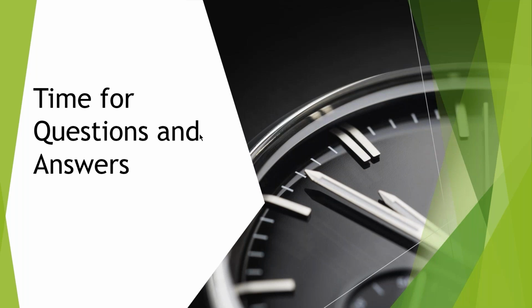For instance, what I was showing here, if you buy really good equipment, have it calibrated in dead weight, you typically will need 2 to maintain 0.2 or better. Most of the people I helped were around 0.3, like I said, we're around 0.35 and they were using 2. But the real answer is it just depends on how good. If you want to drive it down to 0.1, you're probably looking at 5. If you're okay with 0.2, you at least need that 2 to 3. If you're looking at 0.5, you probably only need 1 to 2, depending on what range you want to go. But you really have to do the work and propagate those uncertainty budgets to know where things are.